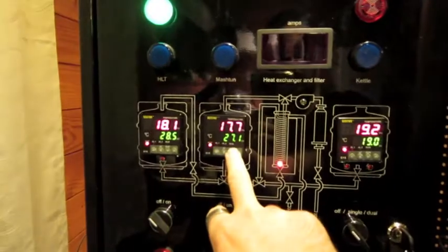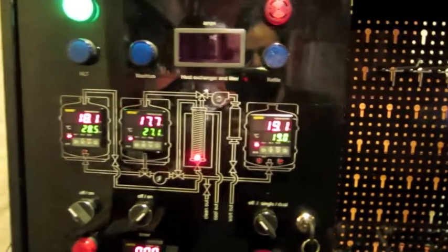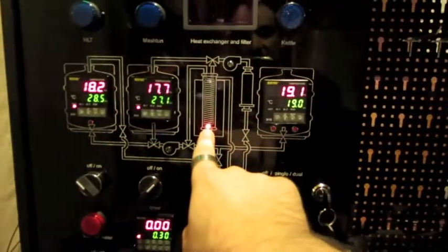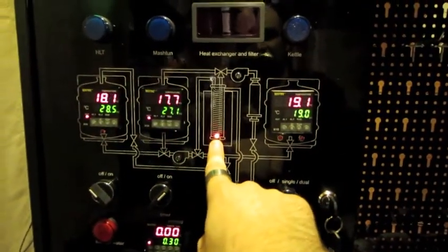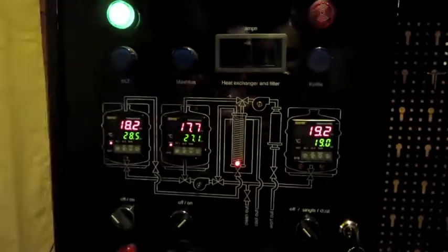Still leaves the power on, still leaves the temperatures on so I can see what the temperatures are, because it would be important to actually know what is going on. The PID lights are still turning on and off, but there's no power going to the element as indicated by the pilot light.